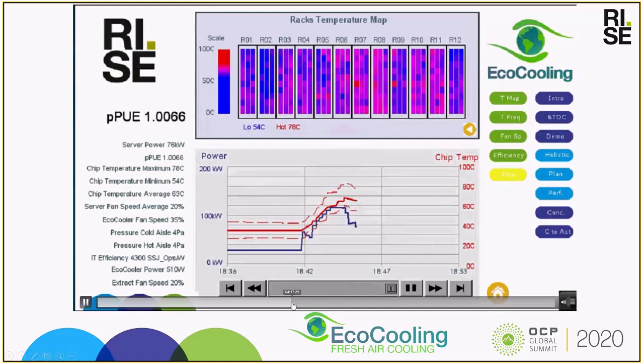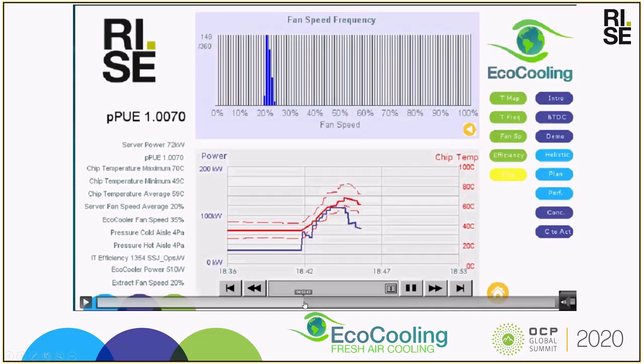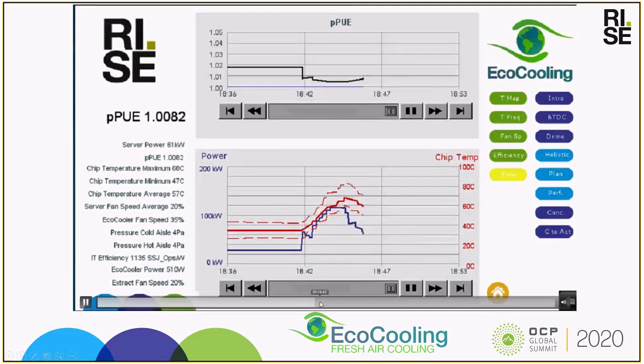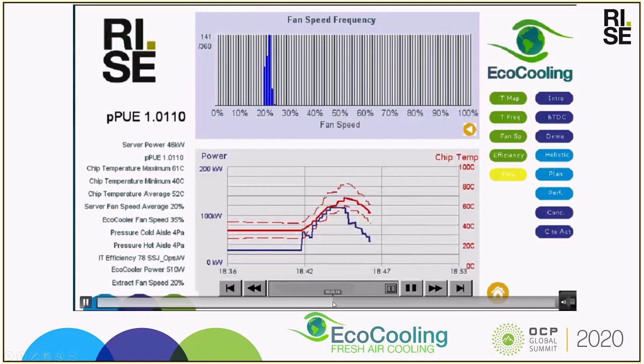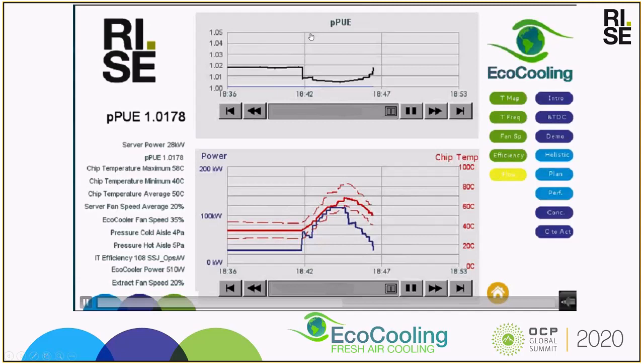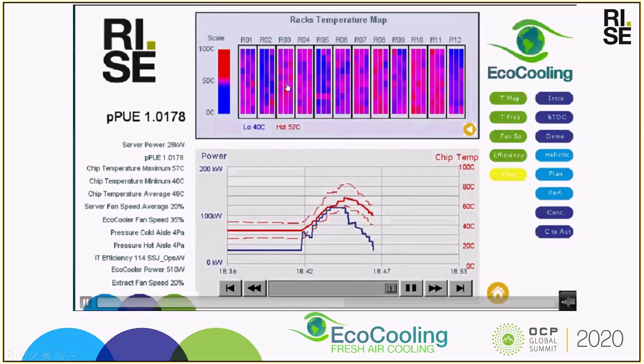As the experiment runs, the fan speeds are all the same, 20% server fan speed, 35% on the cooler fan speeds. And as we go down, now we're down to 28 kilowatts, which is the idle power, and the histogram of server fan speeds has moved to the left. Chip temperatures have dropped down now to lowest at 37 and the hottest at 56. The average is 47.